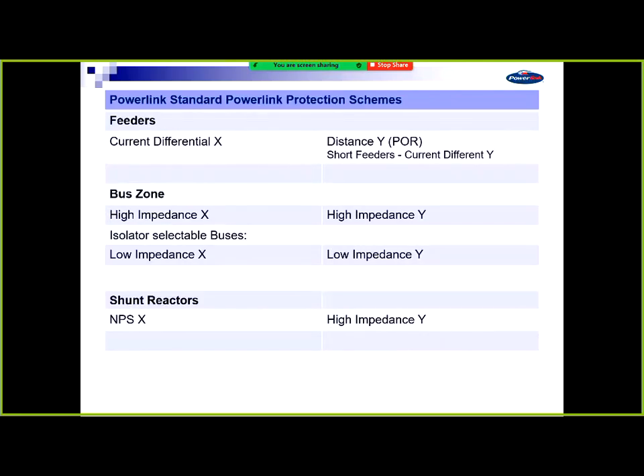So for our feeders, we have a current diff on the X and a distance on the Y. The problem with distance protection is that if you get very short feeders, you can have an issue with the distance discriminating. So we have duplicate current diff on that.